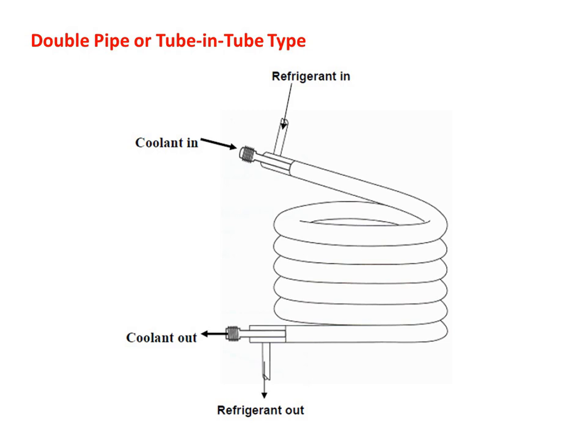In the double pipe or tube-in-tube type condenser, there are two concentric tubes. The inner tube is for the coolant and the outer concentric tube is for the refrigerant. The coolant enters from the internal tube and moves out from the other side. The outer tube is for the refrigerant — this is the refrigerant inlet, and after heat rejection the refrigerant exits from the other direction.